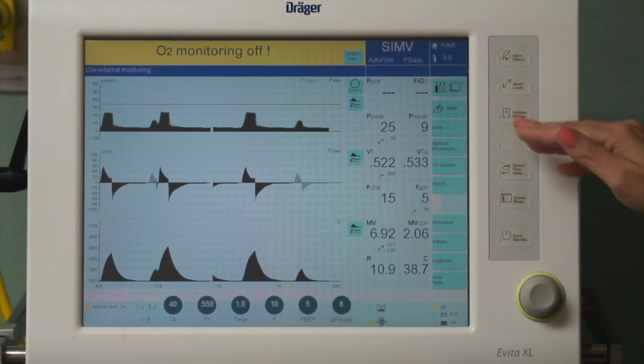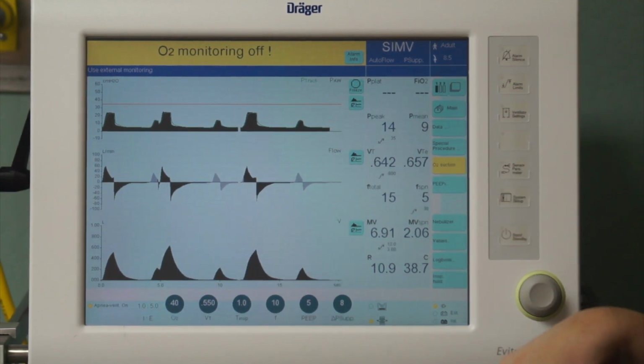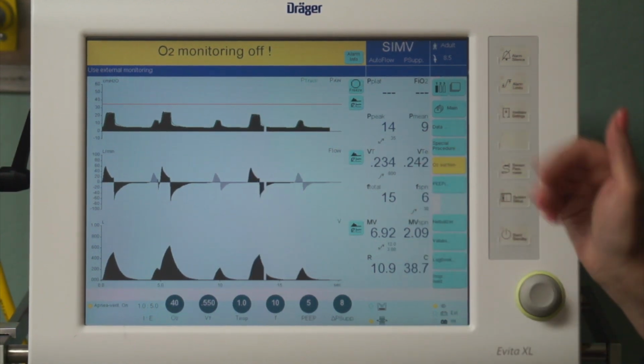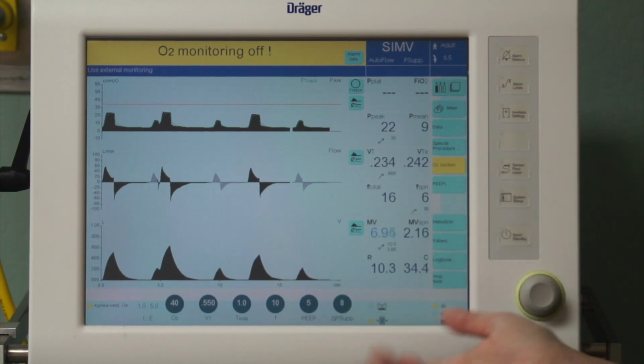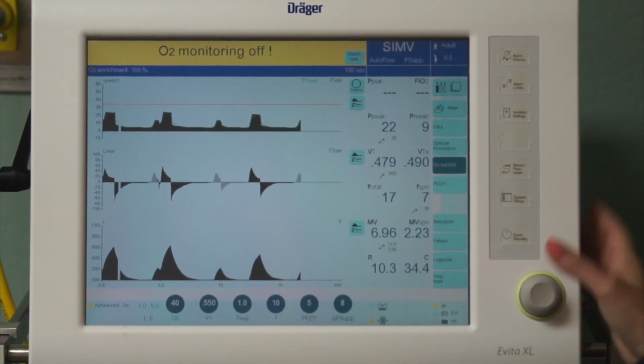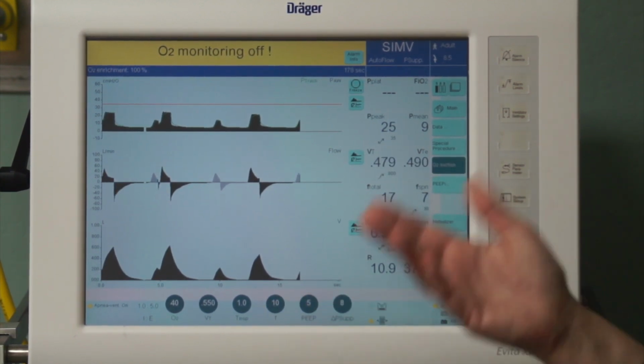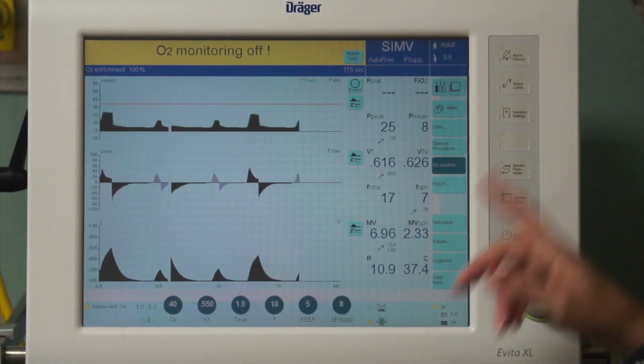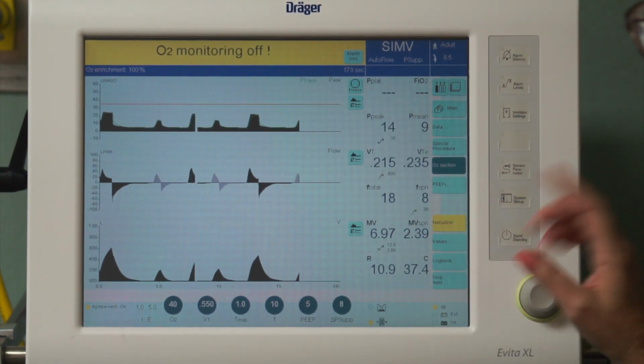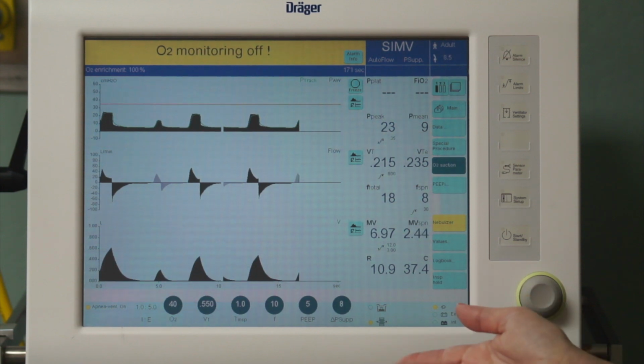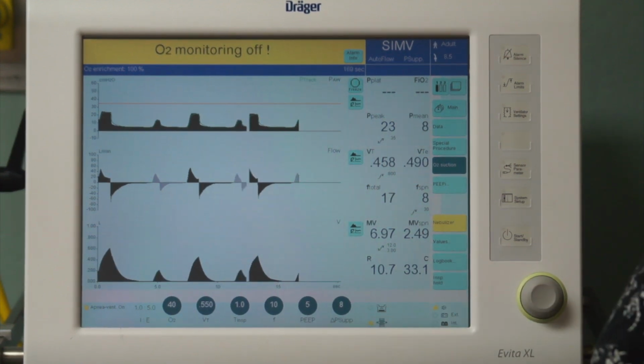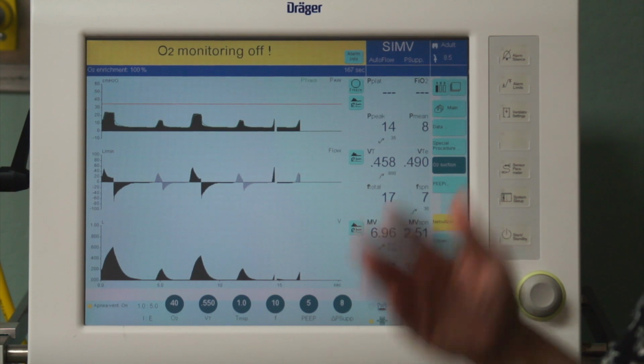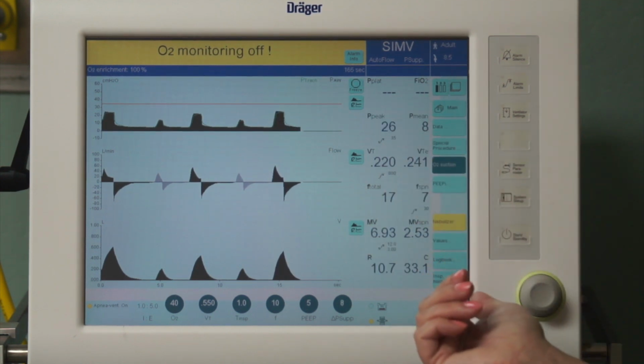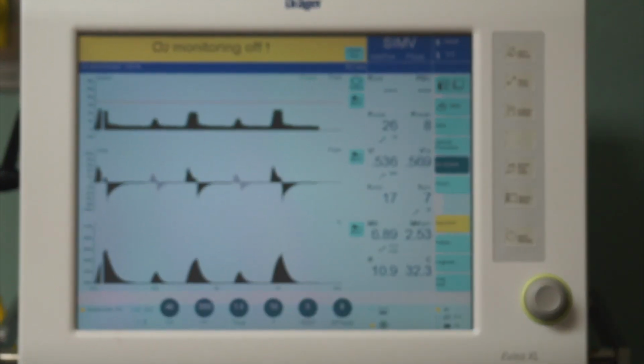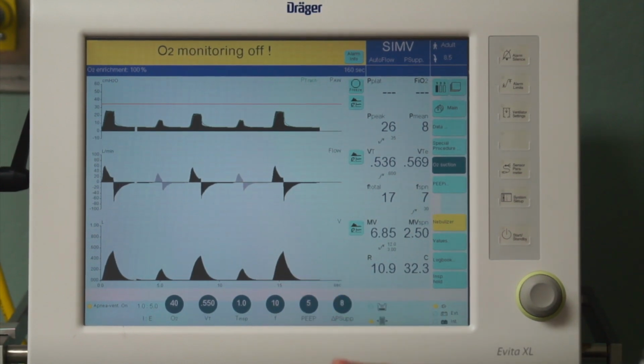Some other functions we have here are things like O2 suction, which is going to turn on the oxygen. It's going to increase your oxygen to 100% so that you can suction the patient. Other things we have here is nebulizer. If you were to run a nebulizer in line and you have that extra flow going to the patient, if you let the ventilator know that you're doing that, it won't alarm. It'll compensate for the volumes and it won't start alarming for you.